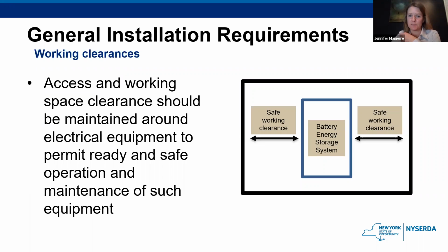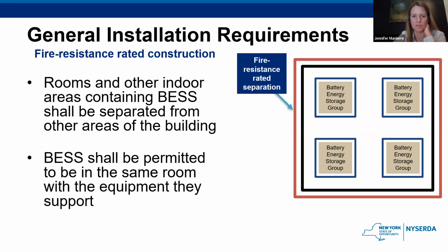Working clearances. Clearance for working on all of the energy storage equipment should be 3 feet. Obviously, they should be unobstructed. Fire departments might go out to do a site visit, and if so, they should notify the owners of the equipment if they're not in compliance with the regulations. Some of these are fairly common sense things. You need to be able to access and maintain the equipment.